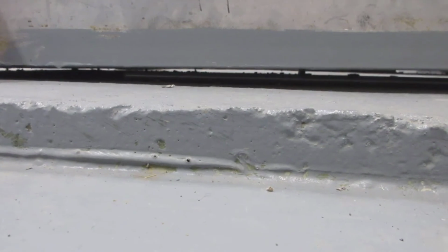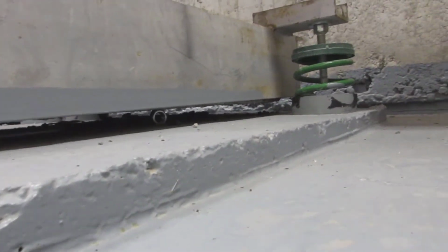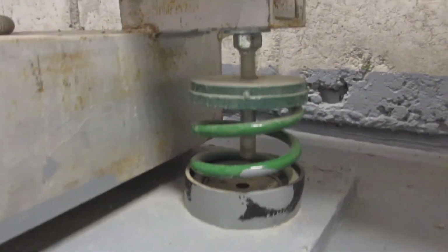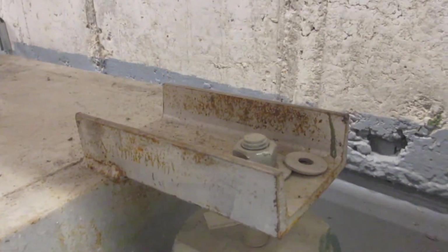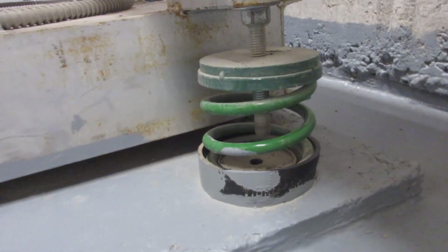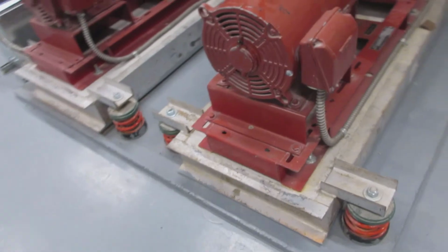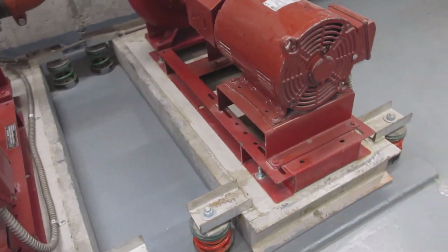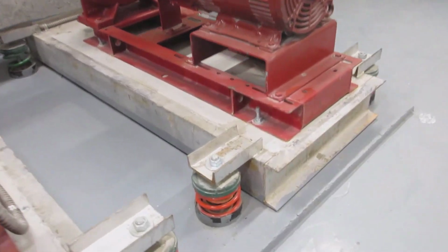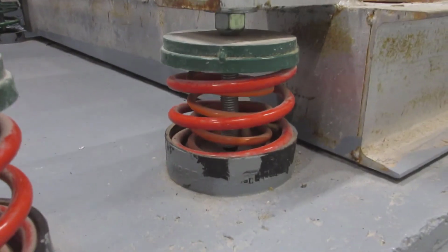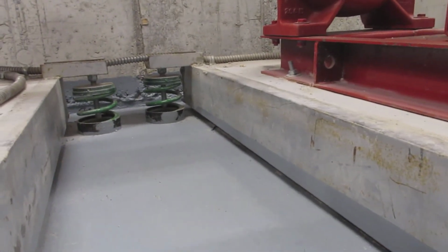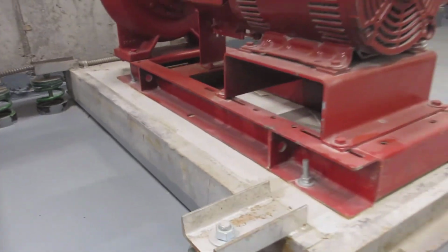Getting down alongside of the base, we can see light under the base, but also some debris which may be bridging the gap between the base and the floor. This isolator appears to be adjusted and secured to the base okay. The gap here appears to be closer to 2 inches. Let's move around to the other side now. The other motor end isolator also appears to be not adjusted or have much load on it. The pump end isolators also appear lightly loaded, but otherwise okay.